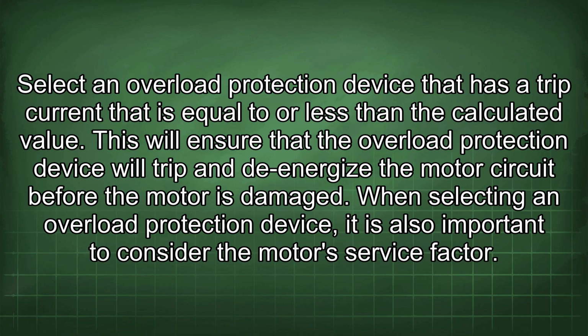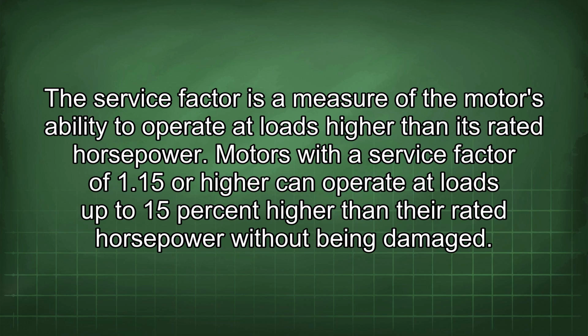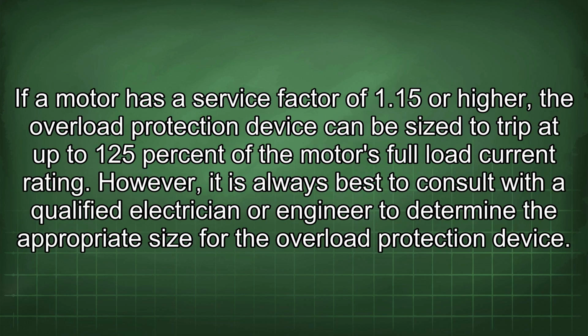When selecting an overload protection device, it is also important to consider the motor's service factor. The service factor is a measure of the motor's ability to operate at loads higher than its rated horsepower. Motors with a service factor of 1.15 or higher can operate at loads up to 15% higher than their rated horsepower without being damaged. If a motor has a service factor of 1.15 or higher, the overload protection device can be sized to trip at up to 125% of the motor's full load current rating. However, it is always best to consult with a qualified electrician or engineer to determine the appropriate size for the overload protection device.